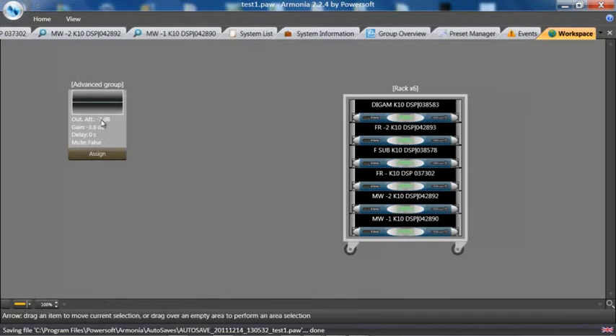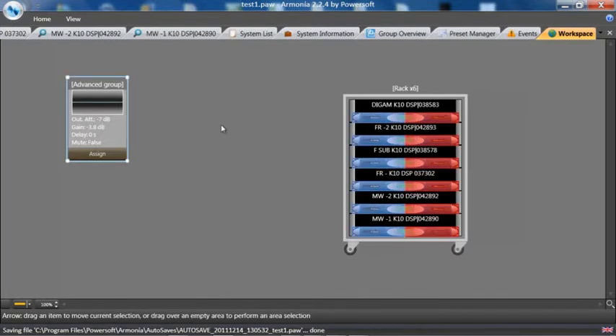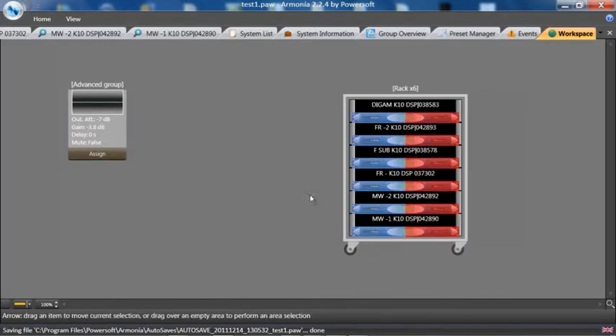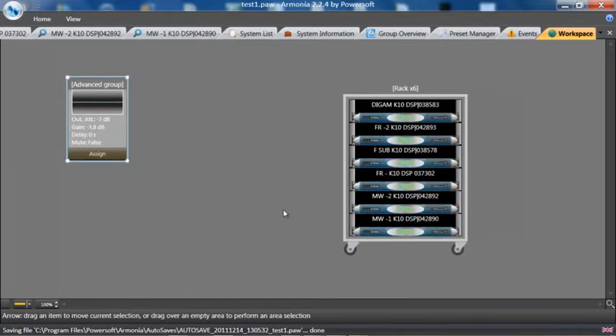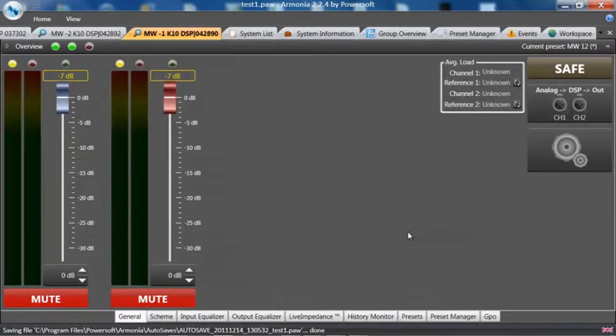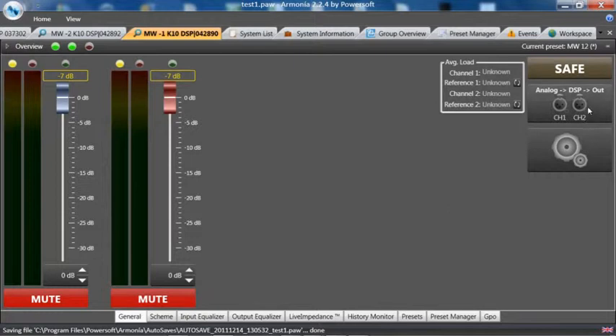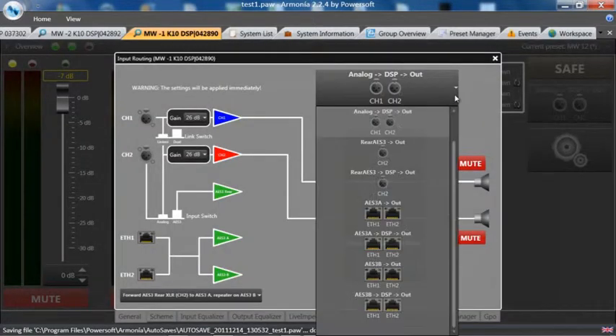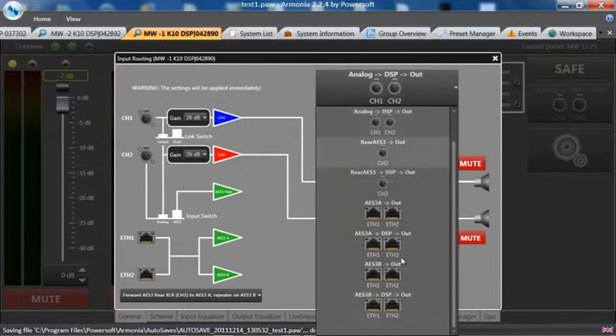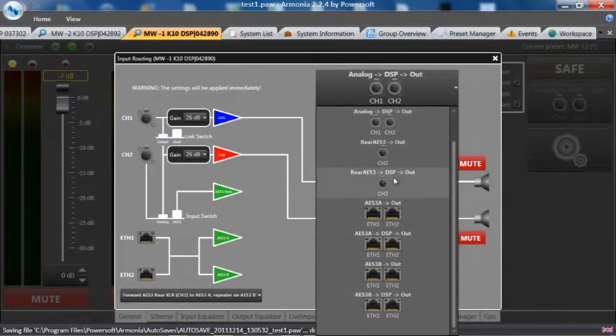They're all set up in this group already. We will leave that, and first thing we want to do is identify what amp will be the transmitter amp, and in this case I have the bottom amp wired to be the AES transmitter amp. So we need to change the routing on the input from analog to AES, rear AES DSP out.